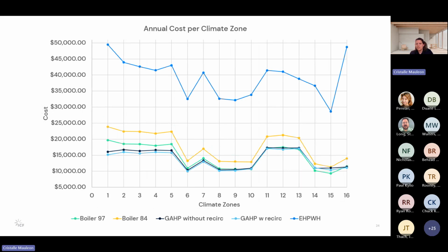This slide is presenting the annual operating cost of the 5 systems measured in US dollars. The boiler at 84% efficiency is yellow. The boiler at 97% efficiency is light green. The GHP with recirculation is in teal. The GHP without recirculation is in dark blue. And then the electric heat pump water heater is in light blue at the top there.